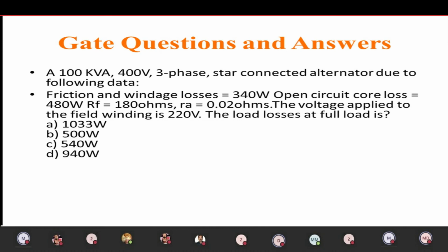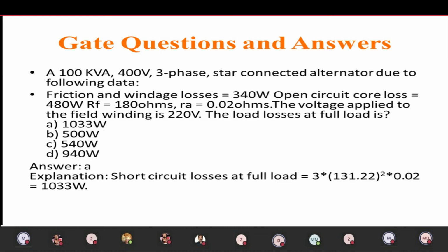So we have four different answers. Let me discuss: the short circuit losses at full load is equal to 3 into 131.22 squared into, from the previous question we take 131.22, into 0.02, we get 1033 watts.